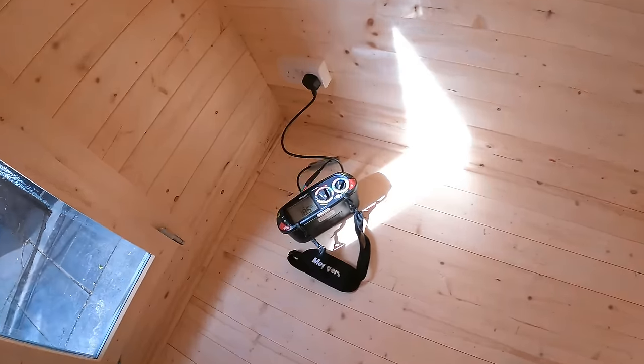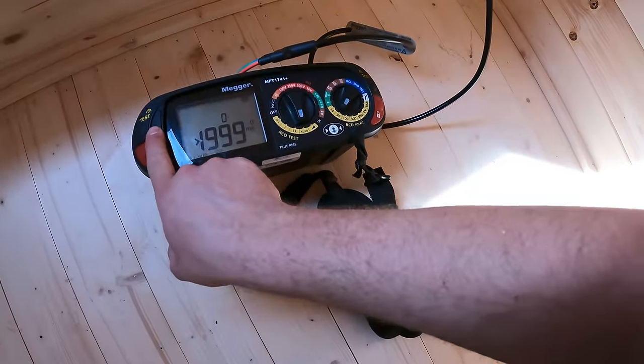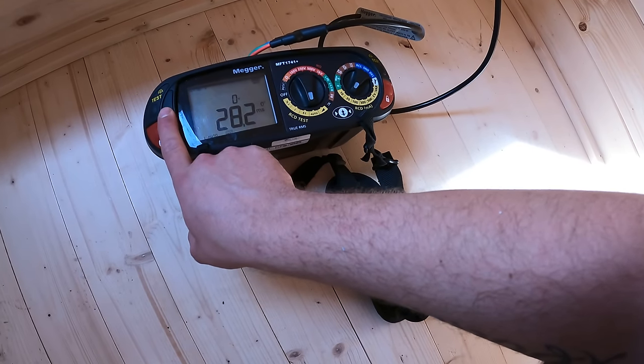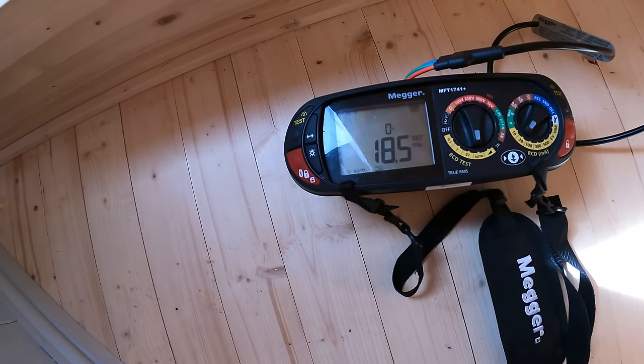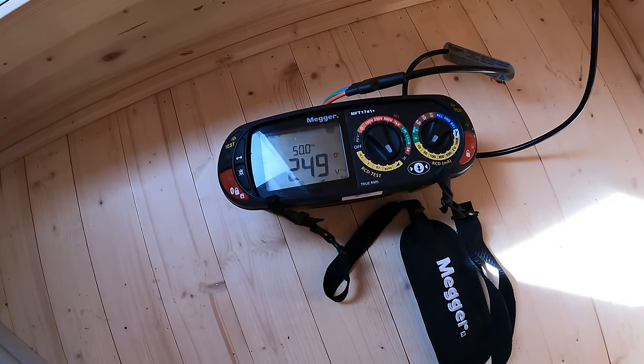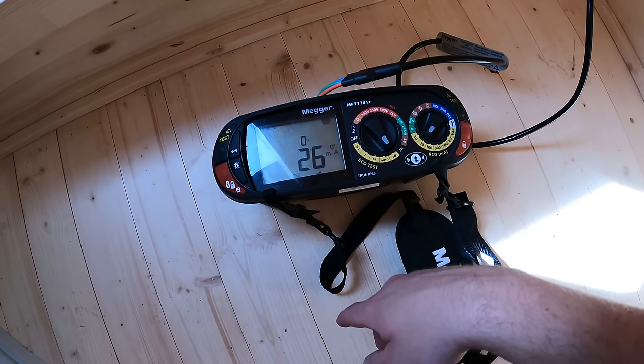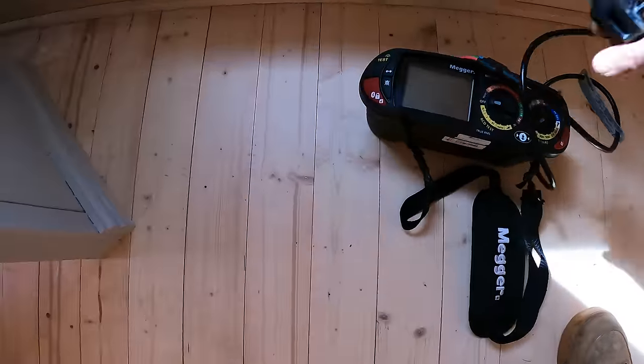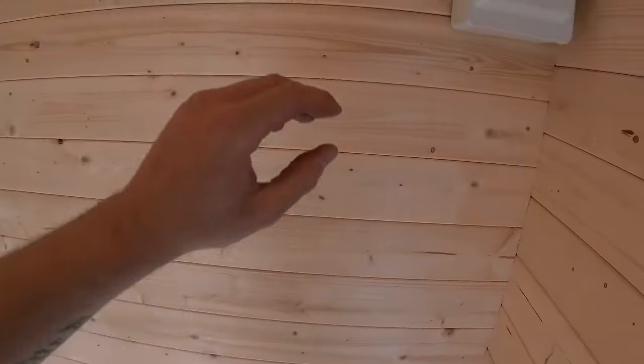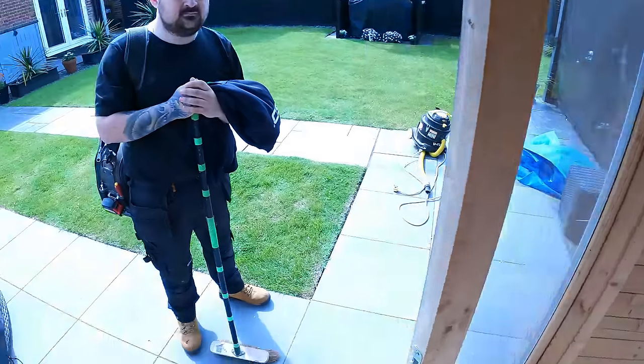Just doing the last bit of testing now. I've had to fill the certificate out on my phone because I forgot to bring the laptop. RCD test - 18.5. Ramped test - 27. Oh, so close. 26. One in 200. We've tidied everything up in there, all labelled up inside. All done in there - tested, certified, certificate sent over to the customer.